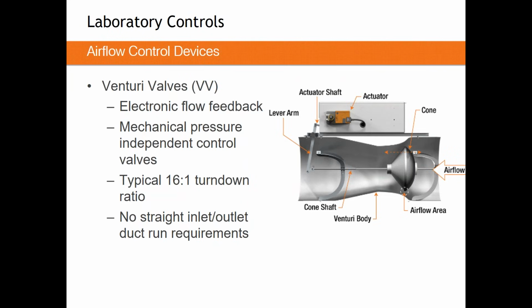For the cone assembly, inside of it is housed a highly engineered spring. As the pressure through the device increases, that cone is going to be pushed farther back into the valve. What you can see there, because of that Venturi shape of the outer valve, the orifice where the actual airflow can go through will shrink. The key to a Venturi valve is balancing how hard the spring pushes back with the size of that airflow area. And basically what you can do here is create true constant volume, meaning without the use of controls or electronics or any sort of brain, through the use of a mechanical system, a force balance really, you can meter that airflow perfectly well and just as accurately as a high accuracy terminal.